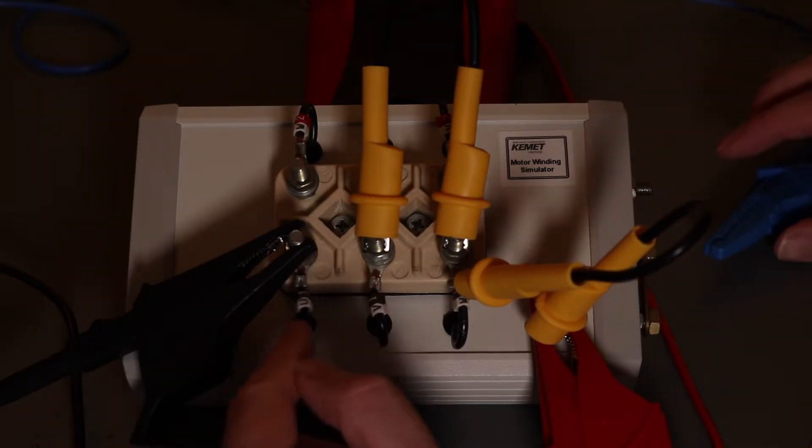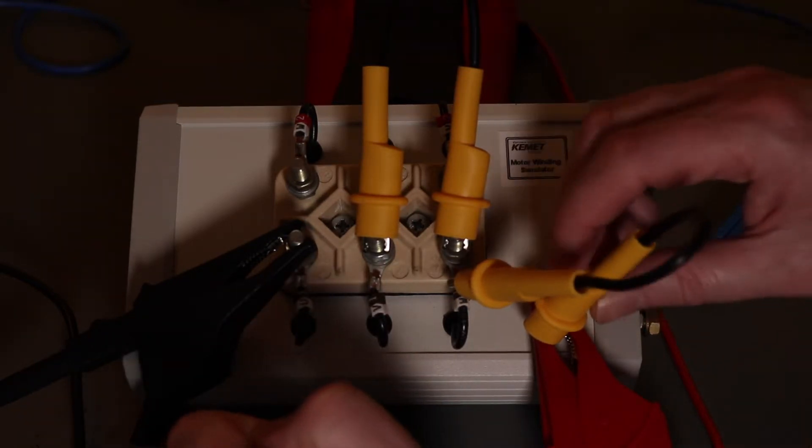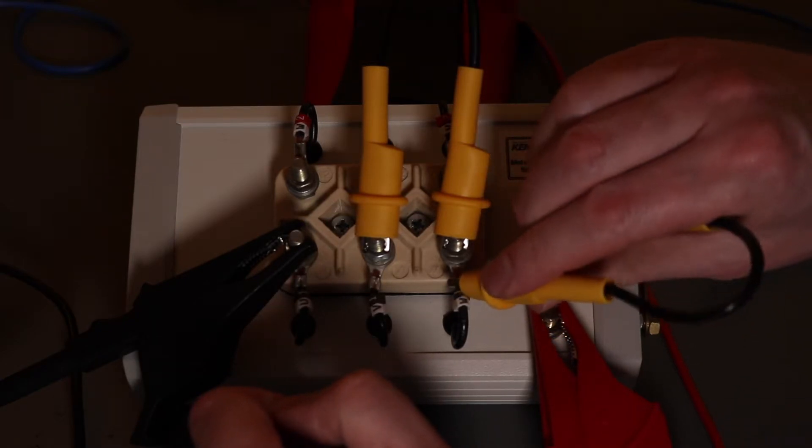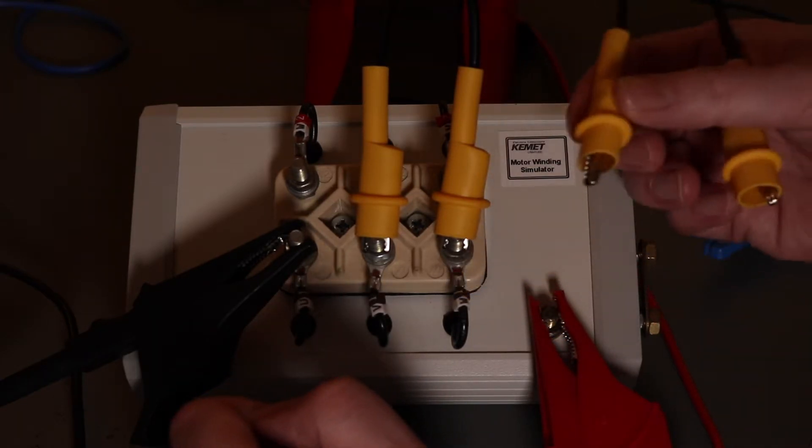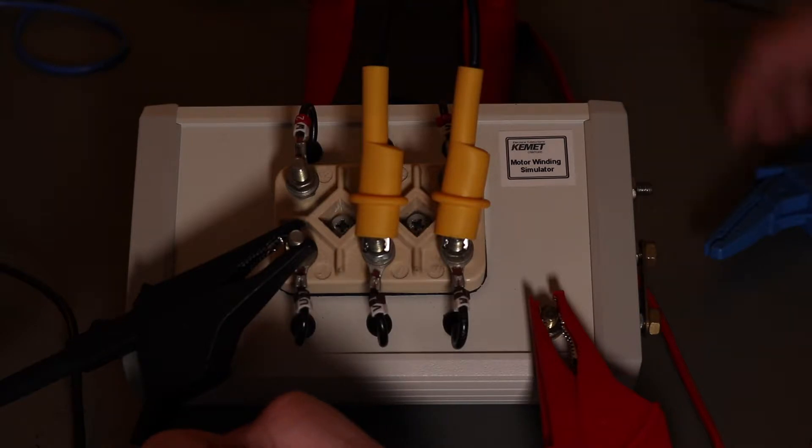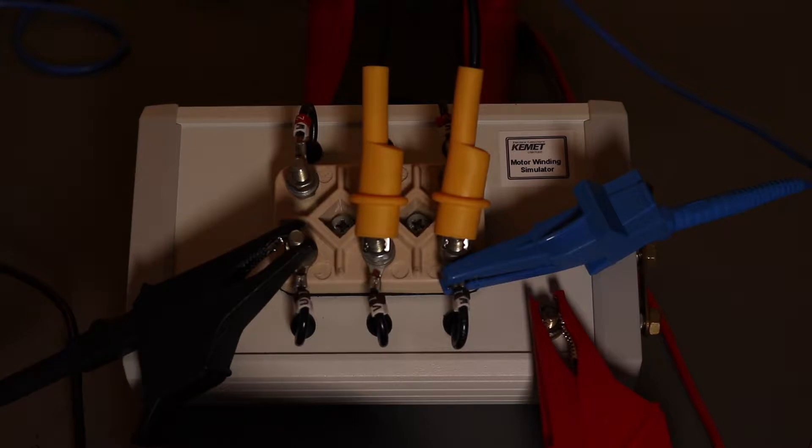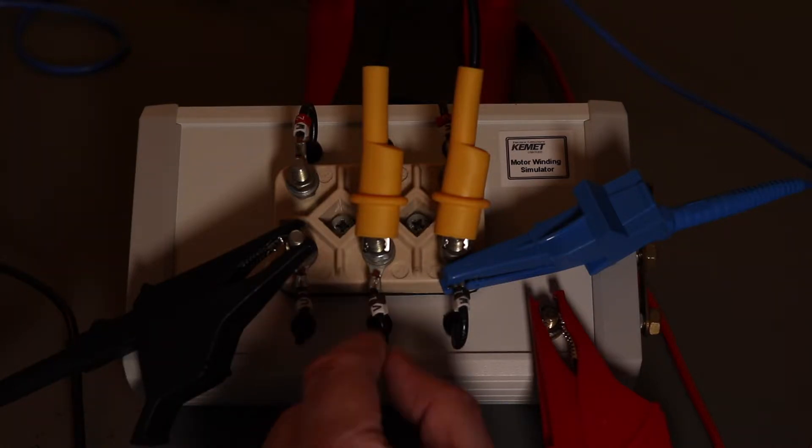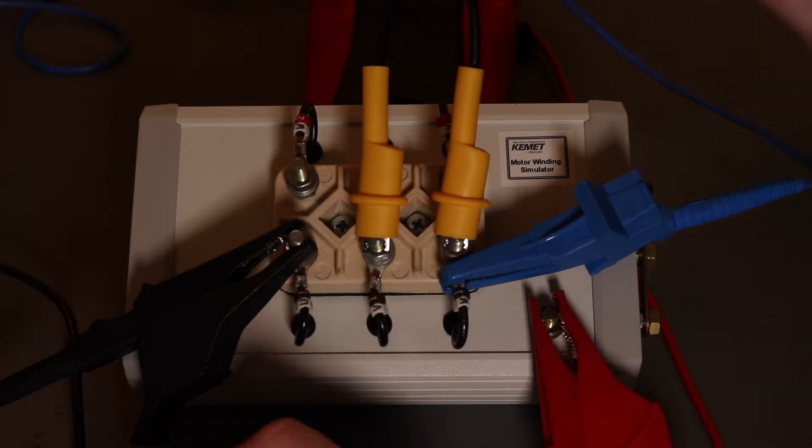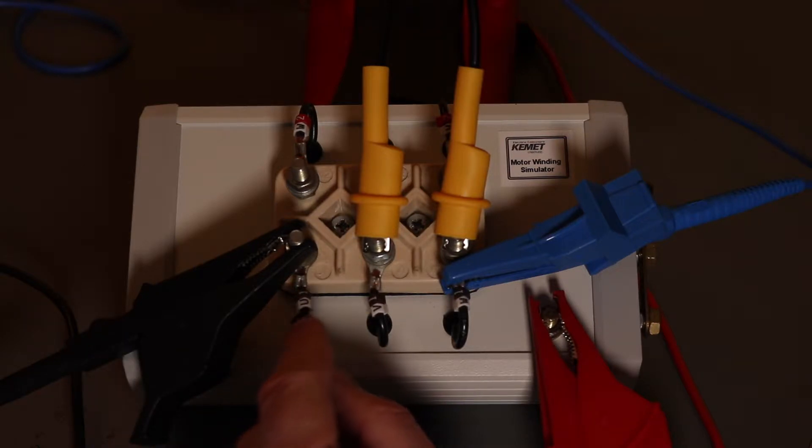To get a true value of this phase just to earth, I can remove the link that takes the two untested phases to earth and I can instead clip the guard terminal on there. Now any leakage from this phase into these two phases goes into the guard terminal and is subtracted from the insulation reading. So that would be a higher reading of just the insulation resistance, the true value of this phase to earth.